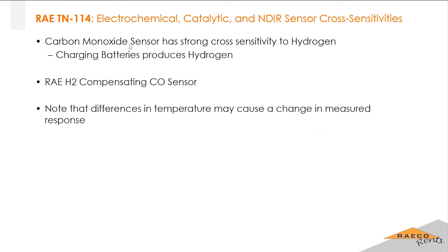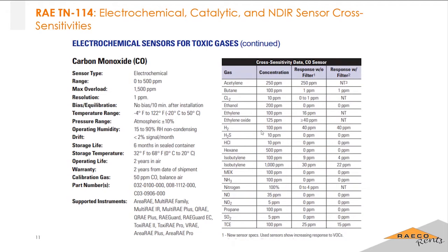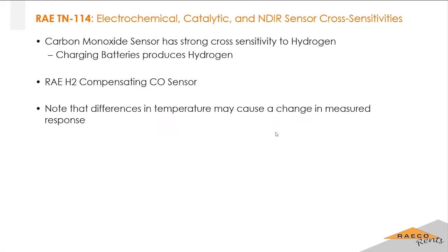There's also a hydrogen compensating carbon monoxide sensor, which can be used in a ToxiRAE or other RAE instruments like a MultiRAE. It compensates the reading for hydrogen. You can see in this sheet that 100 parts per million of hydrogen will get you a reading of 40 parts per million carbon monoxide, which is the reason for this hydrogen compensating sensor. A big application for this is charging batteries, since charging a lot of batteries produces hydrogen, so that's when you'd need this sensor.